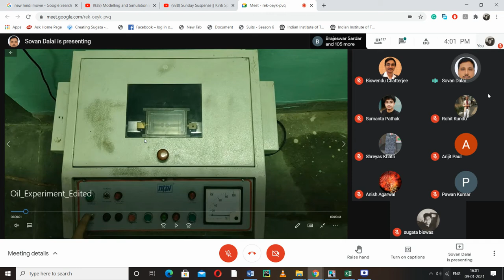Then the high voltage is on. Now you have to increase the voltage. Sorry, this is the high voltage on, and now you increase the voltage. You see the reading gradually increasing. Also observe the test cell. Now you see the gap fires and breaks, and that is recorded in the memory section. If you press the memory button, you will get the voltage at which the gap breaks.